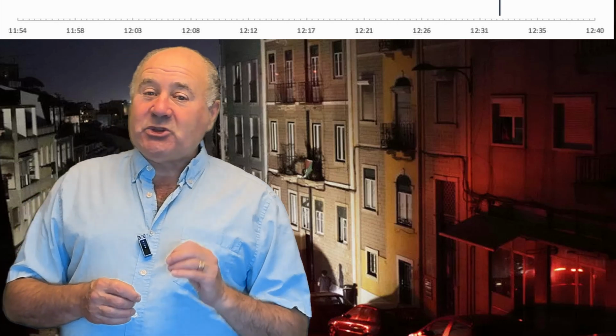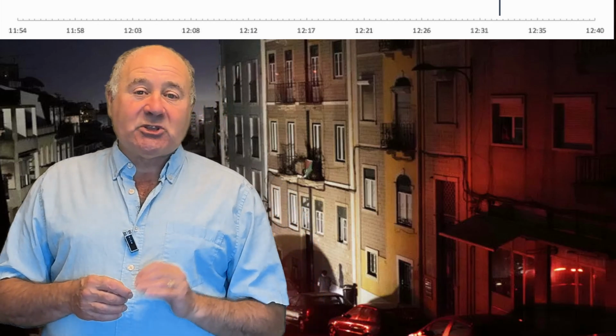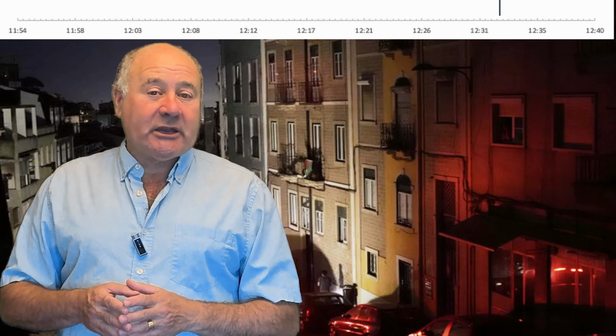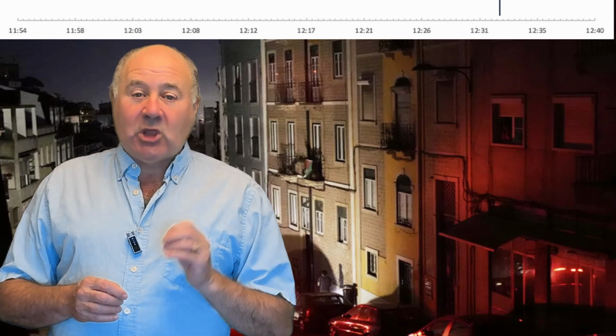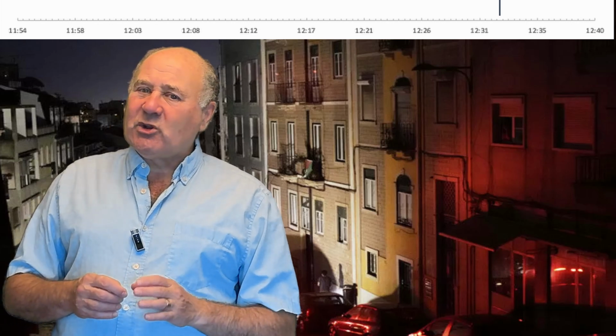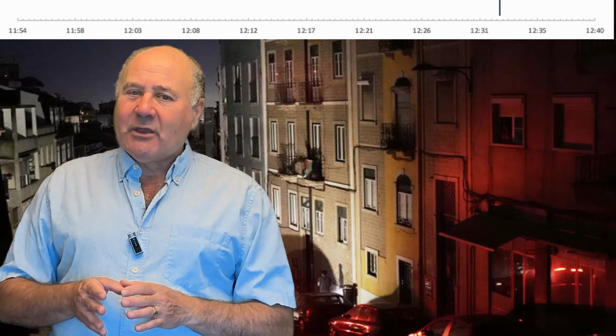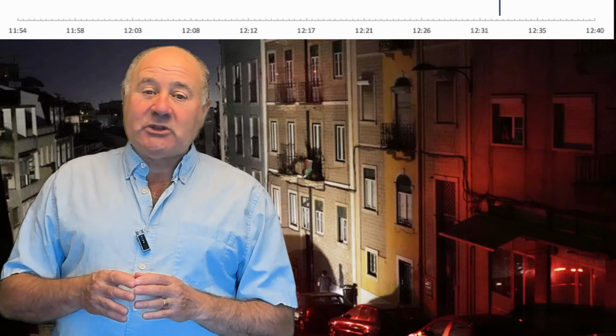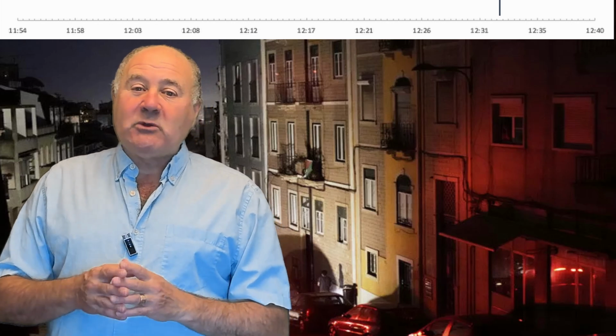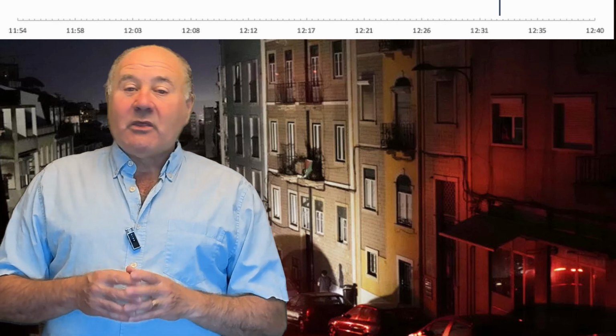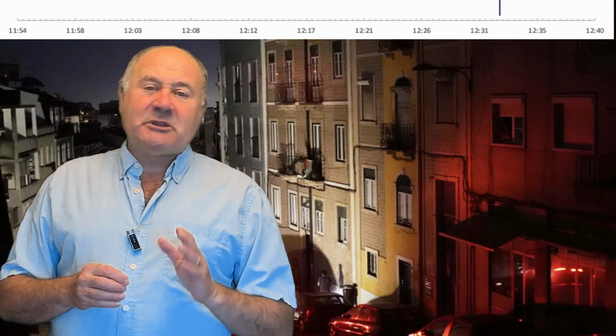At 12:32 and 57 seconds, a trip occurred at a substation located in the province of Granada. The voltage there was low, but not so low that it should have triggered the line to trip. The trip caused the voltage to increase across the grid, but it remained within acceptable levels. The export flow to France dropped to nearly zero.